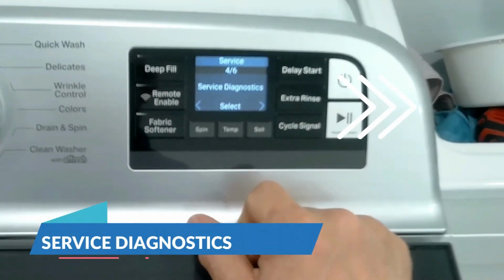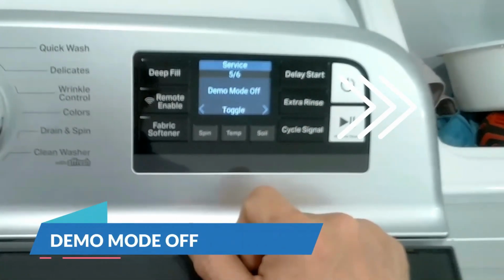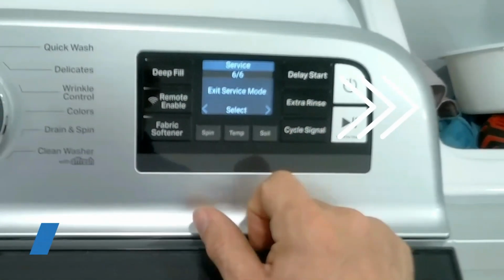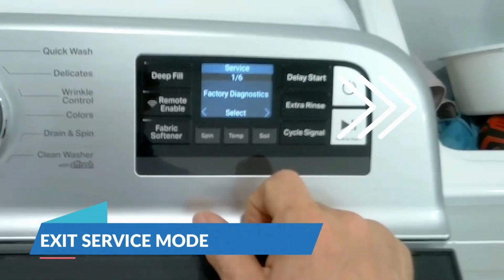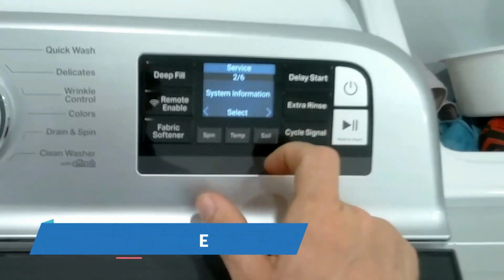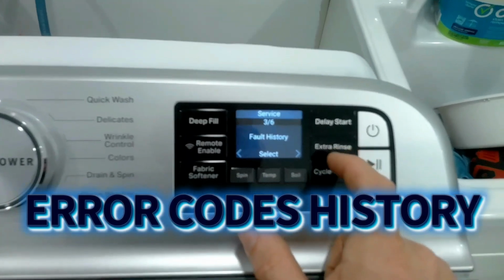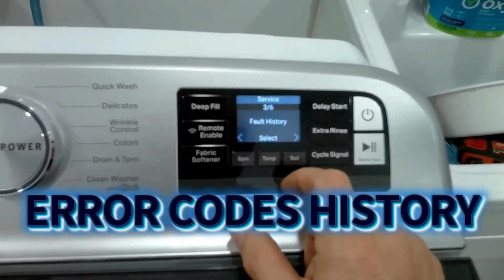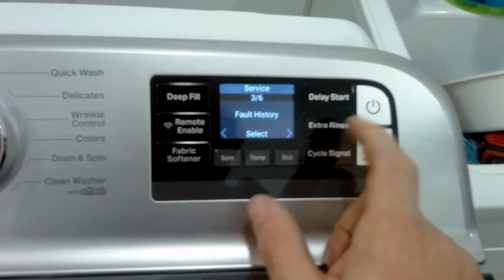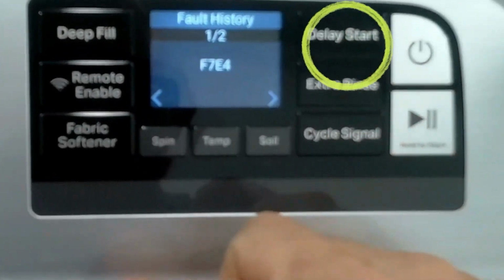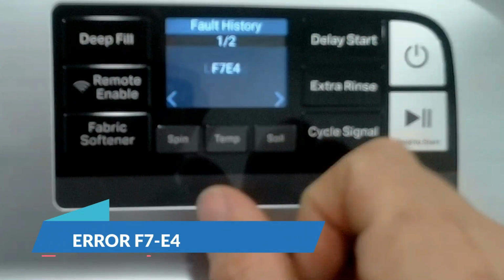This is fault history, service diagnostics, demo, exit service test mode, like if you want to exit factory diagnostic mode. So let's pull up fault history. Once there, hit delay start to enter. And right now you'll see it's pulling up stored error codes.